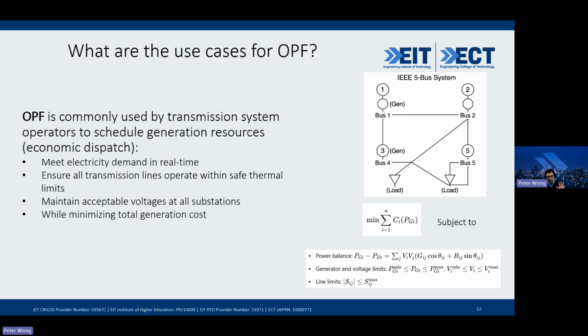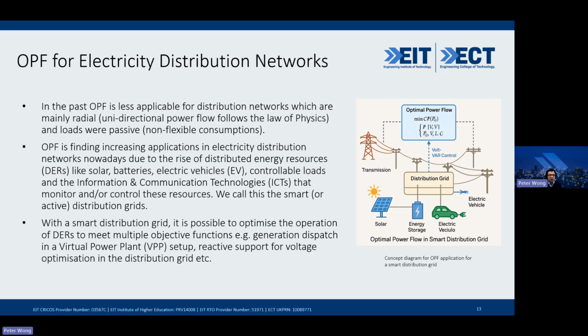But today I'm not really focusing on transmission. We actually see a lot more OPF being applied to distribution networks, which traditionally wasn't the case. The reason is that in the past, distribution networks tended to be mainly radial, meaning unidirectional power flow following the law of physics, basically the path of least resistance, that's where the electrons flow. The loads were also very passive, not flexible consumption—loads were just driven by people cooking or switching lights on.